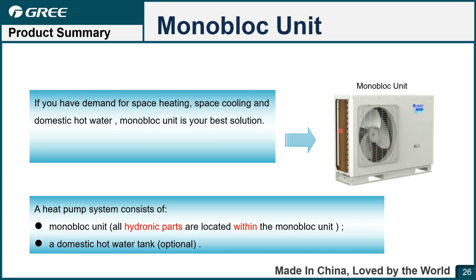Okay. For the monoblock units, it's different. You can see in this picture the outdoor unit dimension is bigger because we integrated almost the hydro box into the outdoor unit. So you can see the size is wider. All of the hydronic parts are located within the monoblock unit.